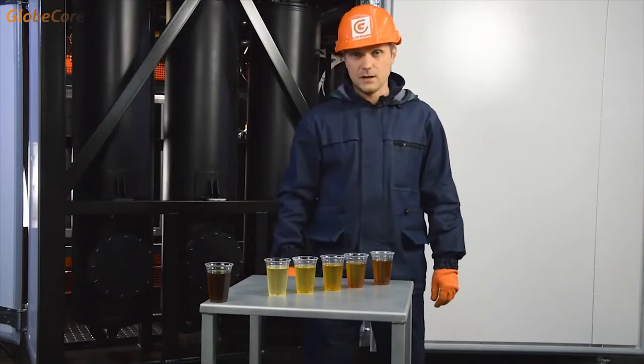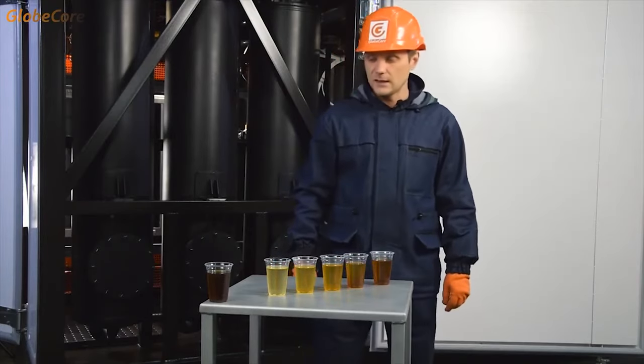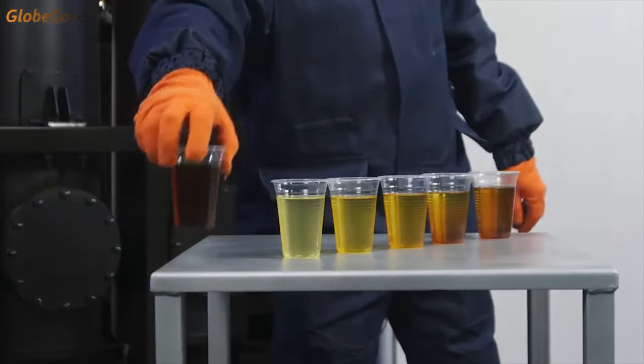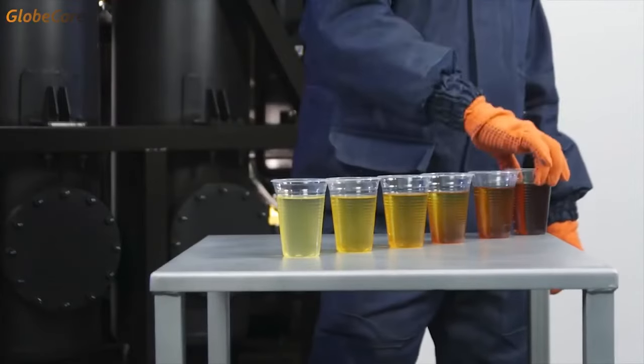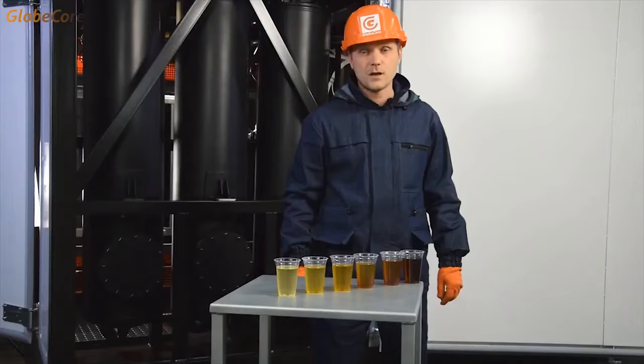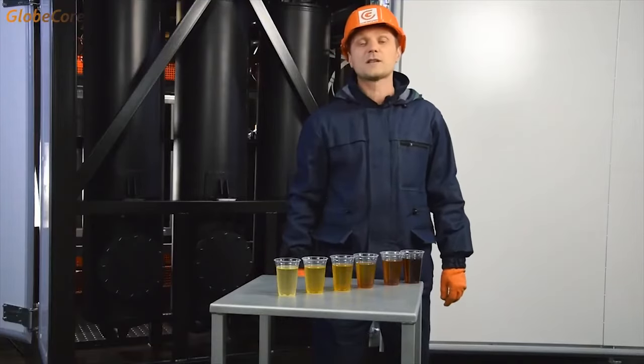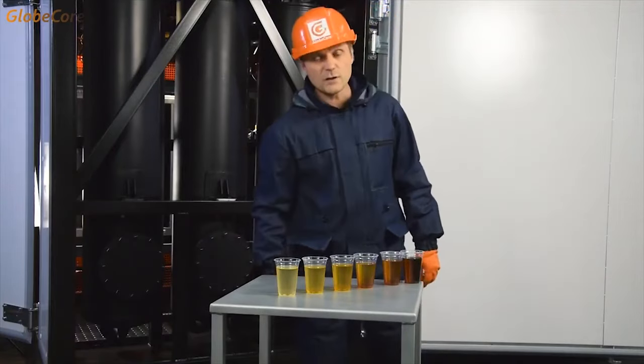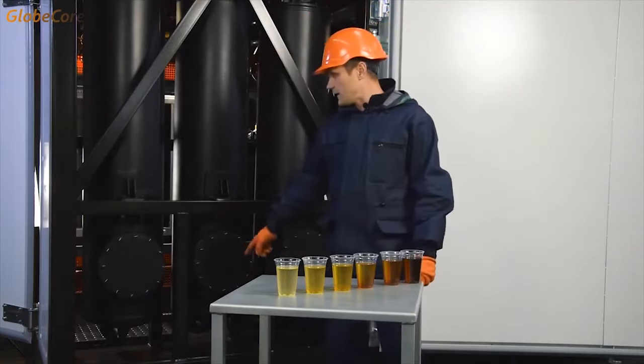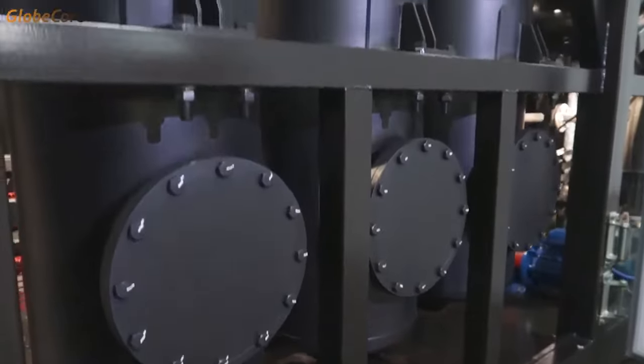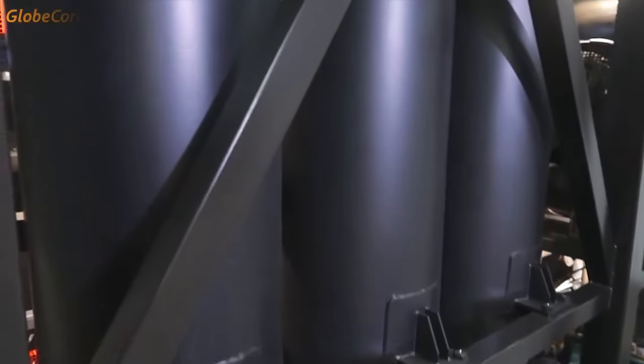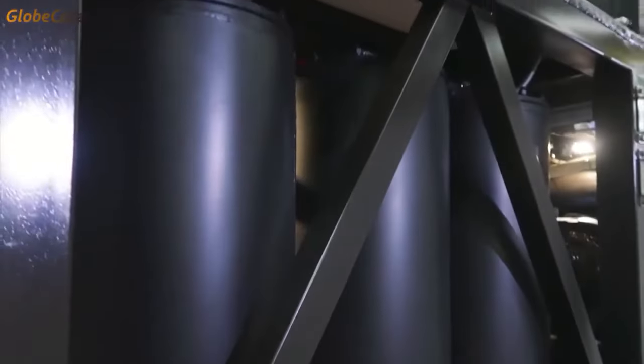Obviously, sorbent life is not unlimited. The quality of the processed oil naturally declines. At a certain point, the sorbent ceases to affect the oil that passes through. This is when sorbent reactivation comes into play. The sorbent is burned at about 600 degrees Celsius. This process fully restores the absorption capacity of Fuller's earth.